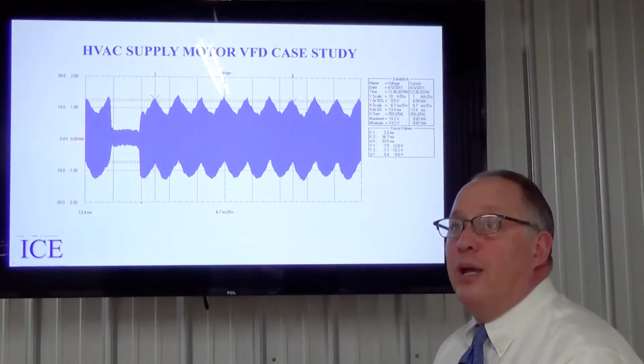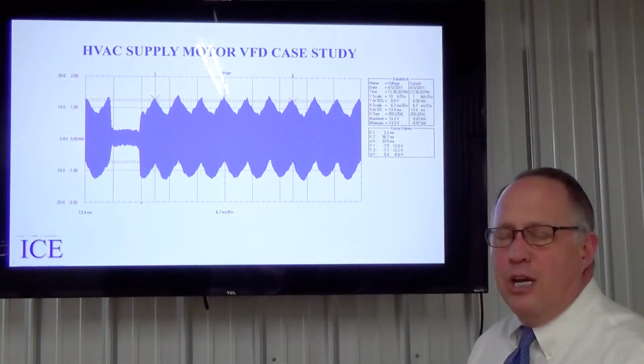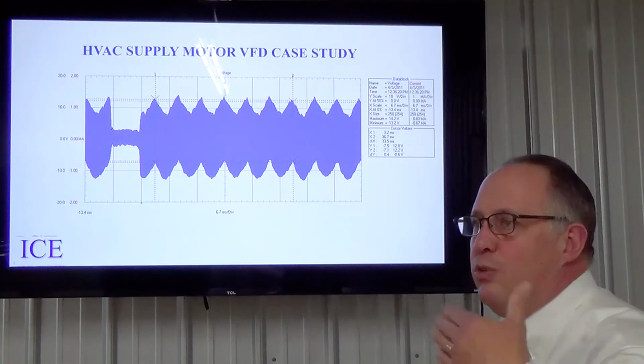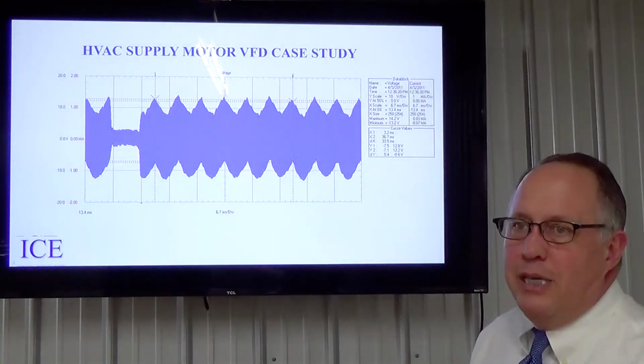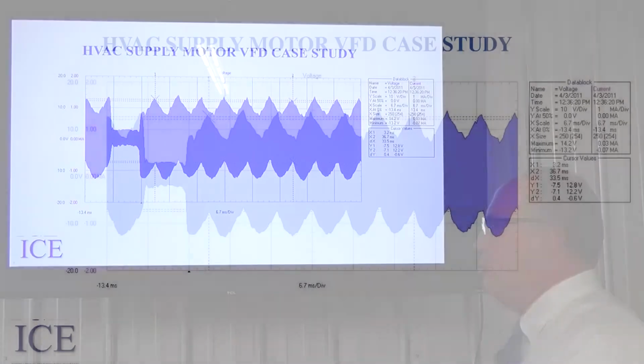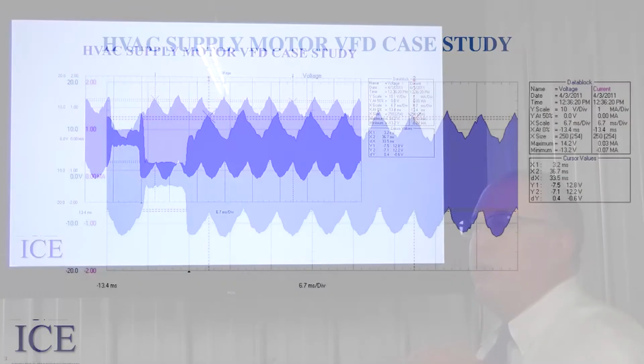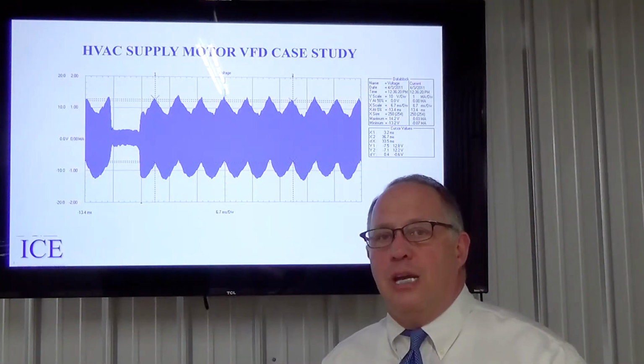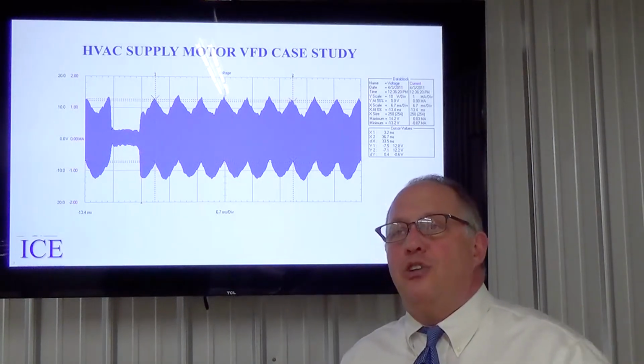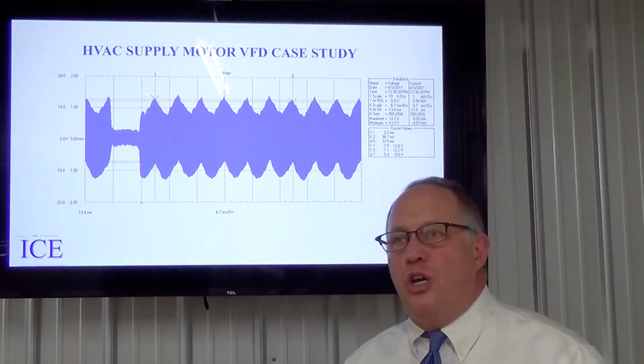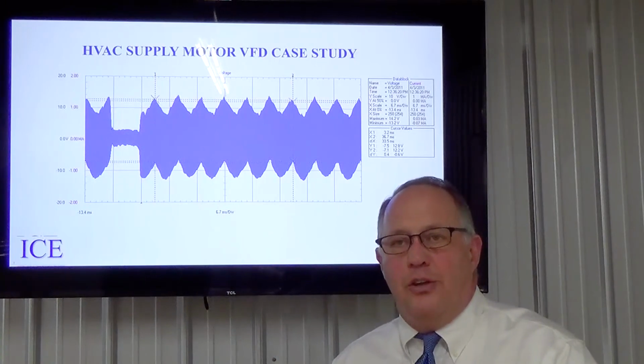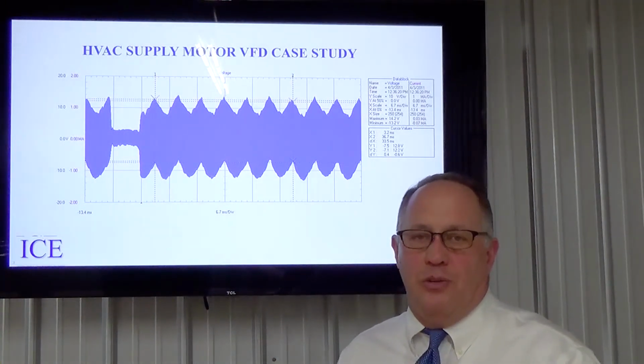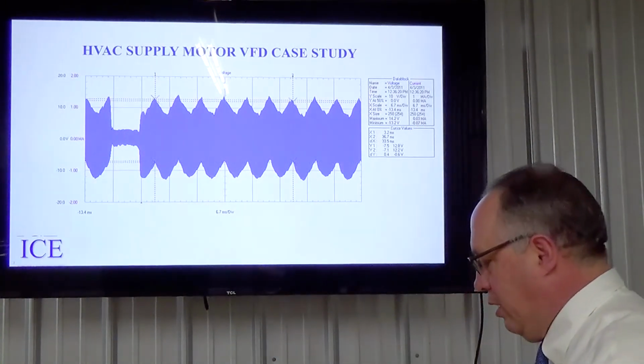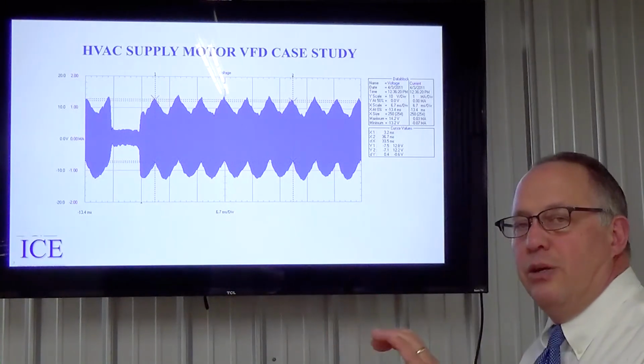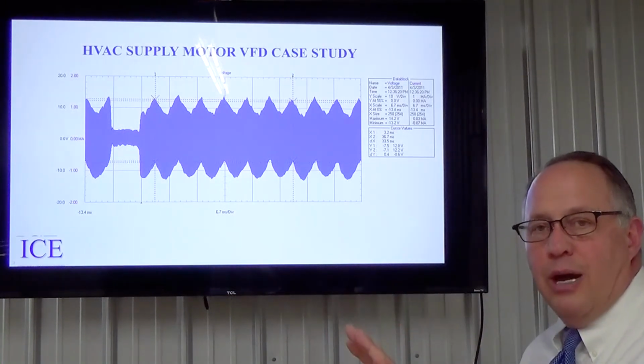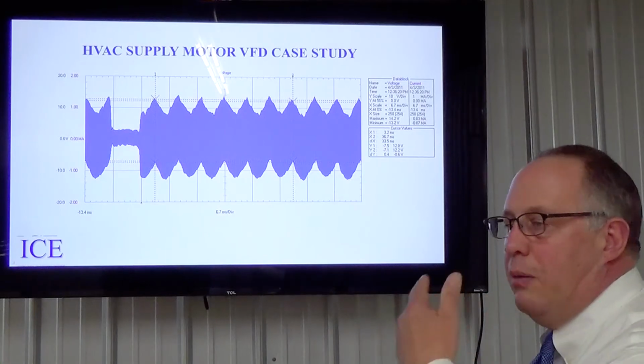This motor had been operating for about a year to 2 years. It was already at the point where it was going to be damaged and fail, starting to make some noise. For this one, the university had dual motors, so you could switch from one to the other so that you can continue operation for their research projects. So we were able to get in. They replaced it with a shaft grounding ring, and problem solved.